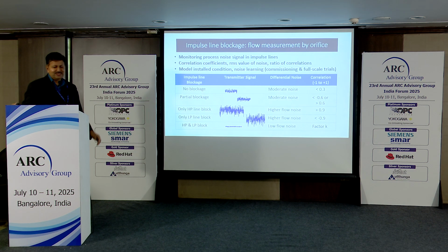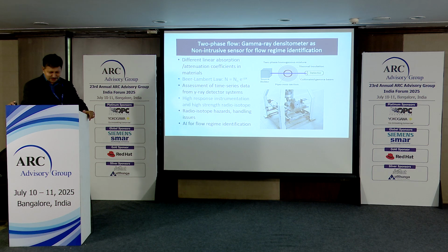The second aspect, the next I'll just move over to, is two-phase flow. We had been fortunate enough to interact with BARC and other agencies in the development of two-phase flow meters, fundamentally for gas liquid flow. The particular requirement where we came in was for safety studies for a loss of coolant accident scenario for heat exchangers in nuclear power plants, and our requirement was to develop a two-phase flow meter with extremely high response time so that we can detect the onset or initiation of bubble formation in high pressure, high temperature water.